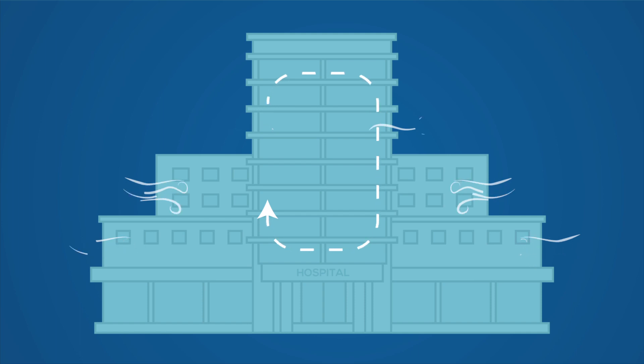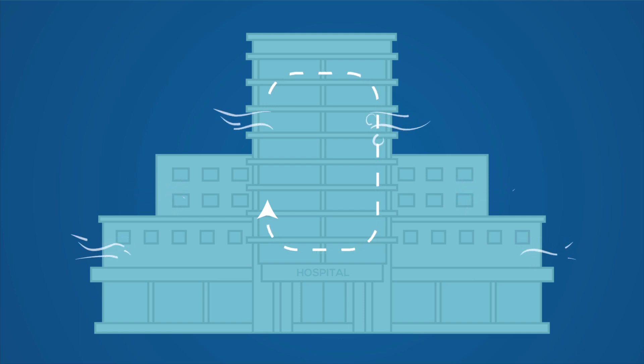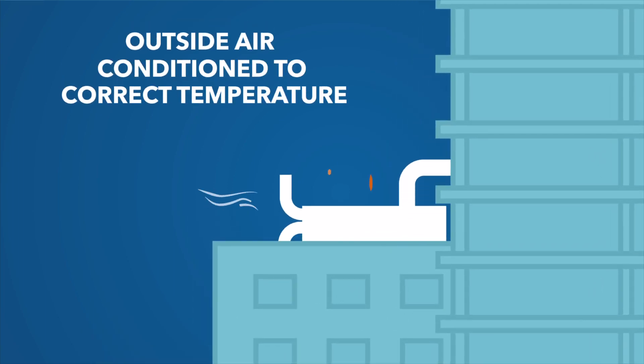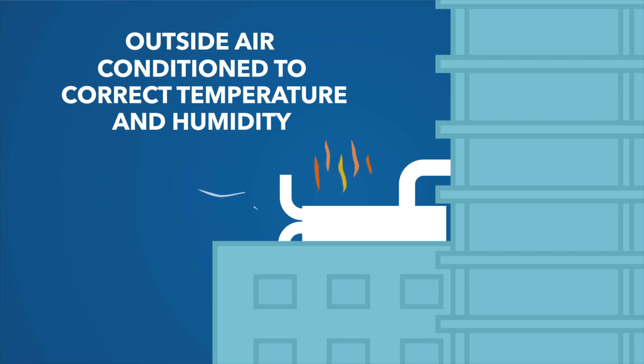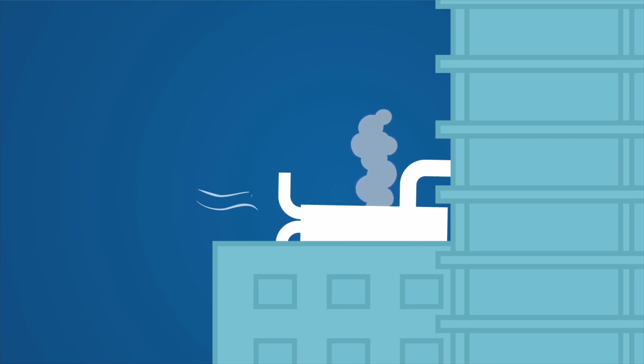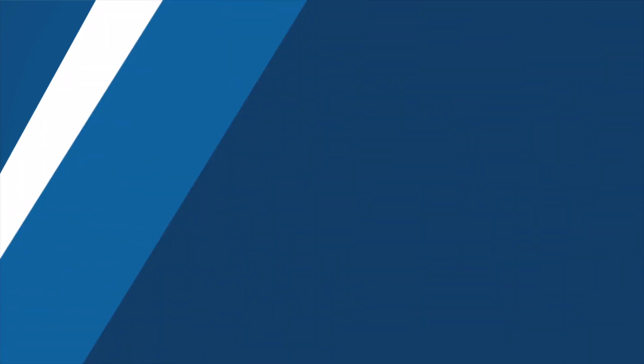However, increasing the amount of outside air can also cause problems. Outside air has to be filtered and conditioned to the correct temperatures and humidity ranges before it can be distributed throughout the hospital. And many of our air handling units were not designed to condition and use 100 percent outside air in the building, so they struggle to keep up.